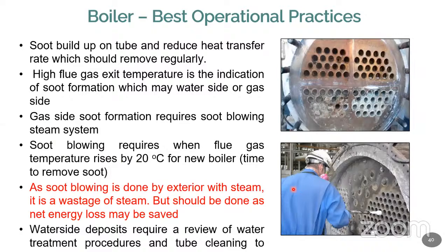Then the best operating practices are very, very important. So these are the tubes I told you about. These are the tubes, fire tube or water tube boilers. Inside the tubes, the water will go or the fire will go. If the fire goes or the water goes, definitely soot formation will be there. Scaling formation or soot formation is always there. If you are passing the fire, automatically soot formation is there. If you are passing the water, scale formation is there. At regular intervals, you have to clean it. Otherwise, what will happen? The heat transferring medium will get blocked because of the soot or because of the scaling. So heat transfer does not take place between the fuel and your water.